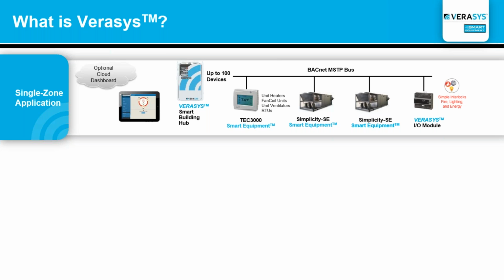In this case it would be what we call a TEC 3000. All of this that you see on the screen right now is plug and play. It uses our equipment model, and that is really the secret ingredient of bringing plug and play into the system. So from an equipment perspective, even if this is a third-party rooftop, it really doesn't make a difference to us, because our controller is what's doing the job of plug and play into the system. On the other hand, if it's smart equipment, we have an embedded smart equipment platform inside of our rooftop, which not only connects to the Verasys system with a plug and play solution, but also has a lot more advantages around fault detection diagnostics, as we talked about earlier, and a lot more information about what your system is doing within the rooftop itself.